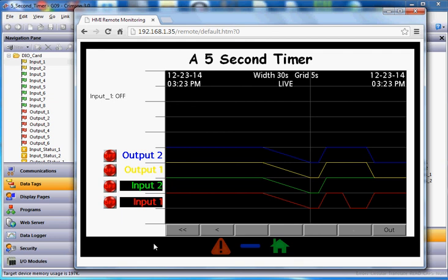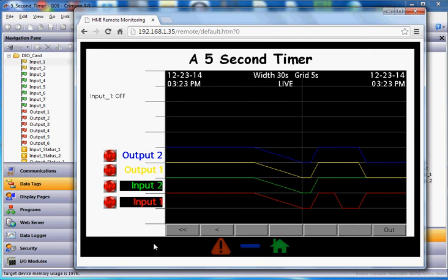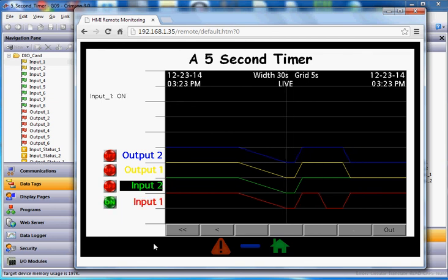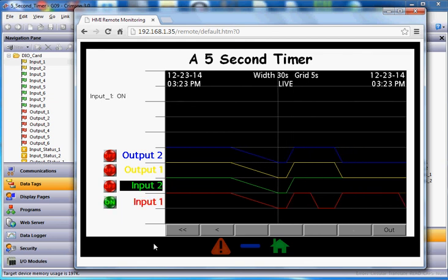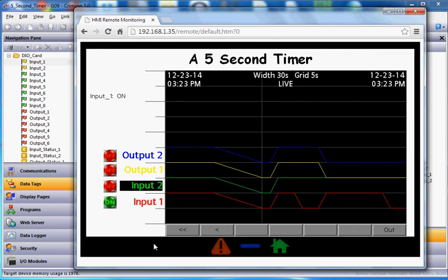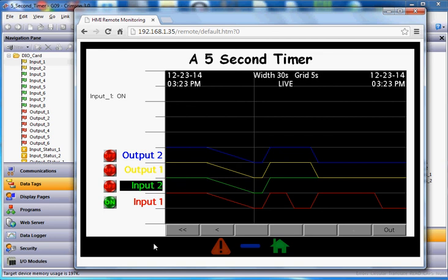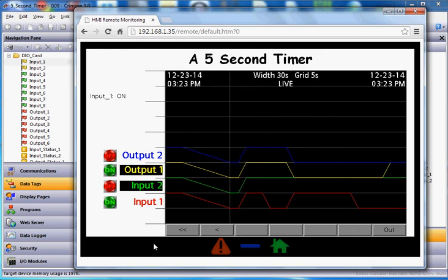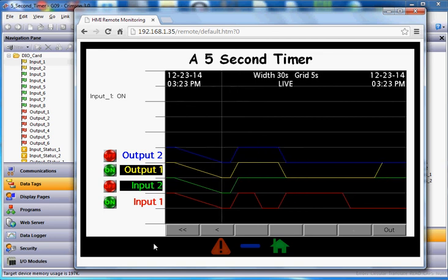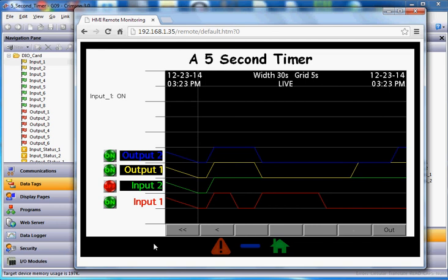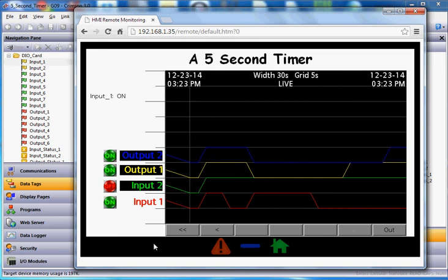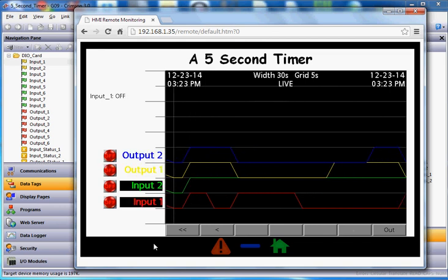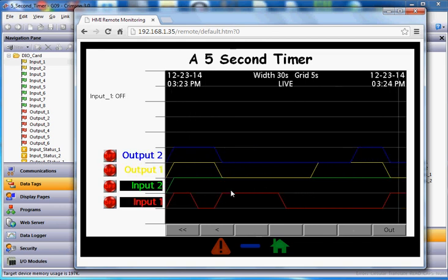So here we go, we're going to try this. Input's off. Go ahead and hold it on here. There is five seconds, first output goes on. Another five seconds, the next output should go on. And you can see it there, the blue line. And if I let go of it, they both go off right away. I just got to invert these.